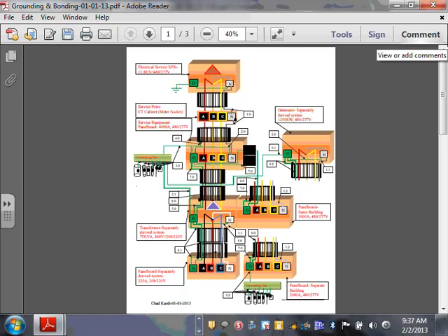Any comments, guys? Am I missing anything about, like, we talked about delta. Anything here missing? Yes, sir. You're confusing me because they have a weird delta center-tapped, and then you have a wild leg. Oh, that's a grounded delta. Yeah. That's a grounded delta. Yeah, you're absolutely right. That's a grounded system. That's not a delta. A grounded center tap, grounded delta is a grounded system. It's not a delta. Delta is an ungrounded system. Yeah. Or center open delta, center tap. These are all grounded systems.